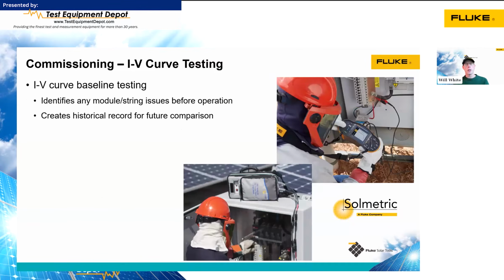Another test that's done during commissioning is IV curve testing. This is checking to make sure that our modules or strings of modules are performing the way they should be. We typically see utility scale projects being IV curve tested at commissioning, and they'll oftentimes test the entire system. We don't usually see IV curve testing in residential or even small commercial systems at the time of commissioning. It's more used for troubleshooting in those applications.